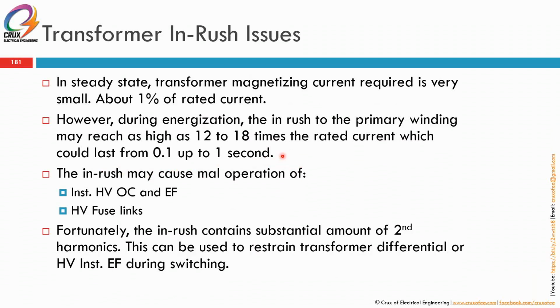So ni transformer tu memang besar lah, 50-60 MVA. And then the inrush may cause maloperation of the instantaneous HV overcurrent and earth fault, ataupun boleh menyebabkan HV fuse link to fuse lah, to melt or to break lah. Fortunately, this inrush ni, they contain a lot of second harmonic punya content. So this can be used to restrain transformer differential or high voltage instantaneous fault lah during switching. So this is inrush punya issue, 12 ke 18 kali lah.